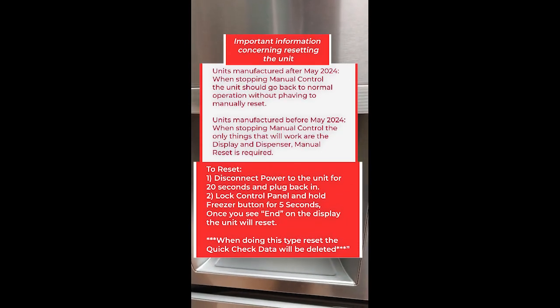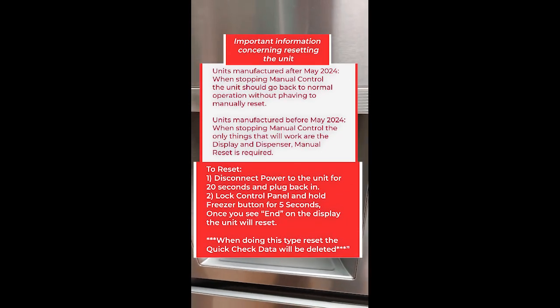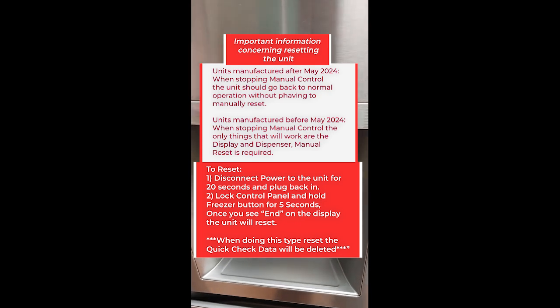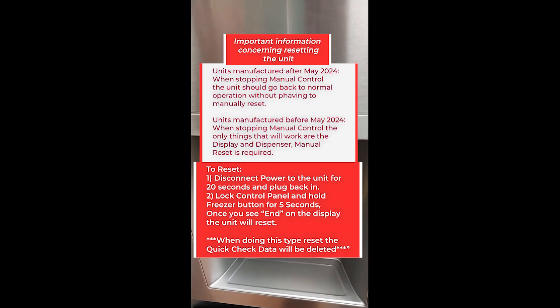Important note: units manufactured after May of 2024, when you come out of manual control, should automatically reset and go back to working and cooling. If the unit was manufactured before May of 2024, when you come out of manual control, it'll be in the state you see here.